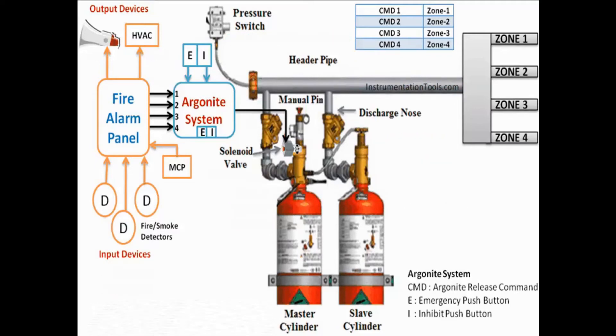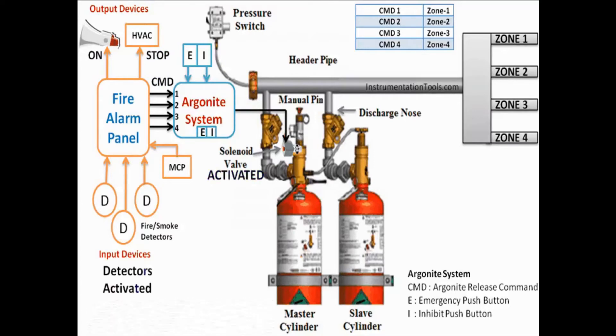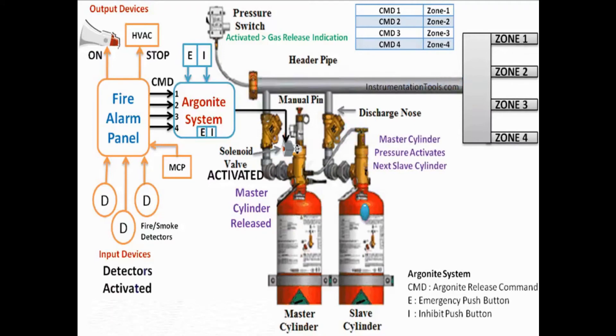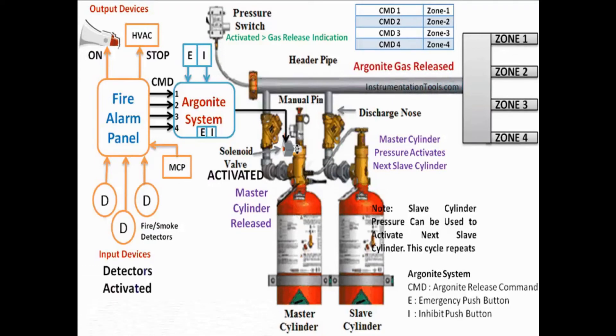If inhibit is not given and after the time delay, the argonite system activates the solenoid valve on the master cylinder. The master cylinder gas is released and has two paths: one is the main discharge line, and the second goes to the next slave cylinder. The master cylinder pressure activates the slave cylinder, which is then released. Similarly, the slave cylinder may also have two paths — the main discharge line or the next slave cylinder. Like this, we can release many cylinders connected in series by activating one master cylinder.